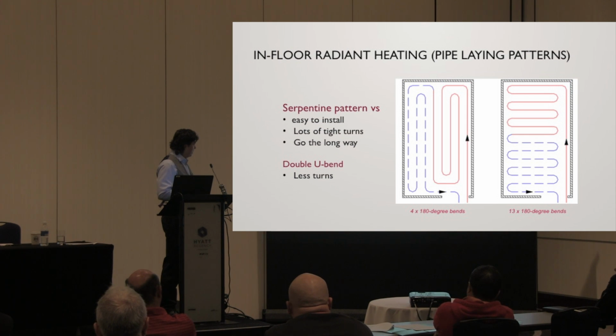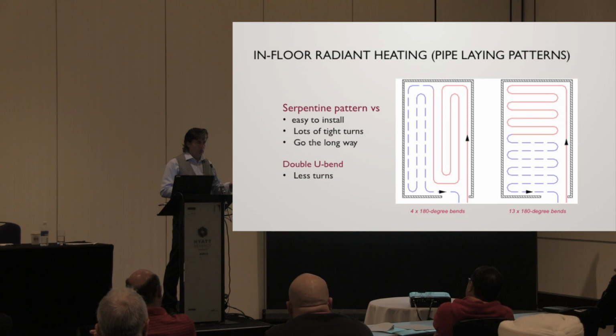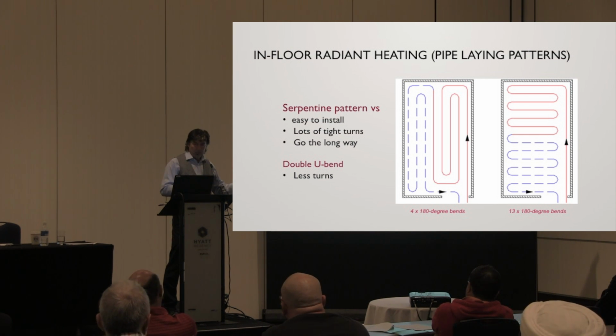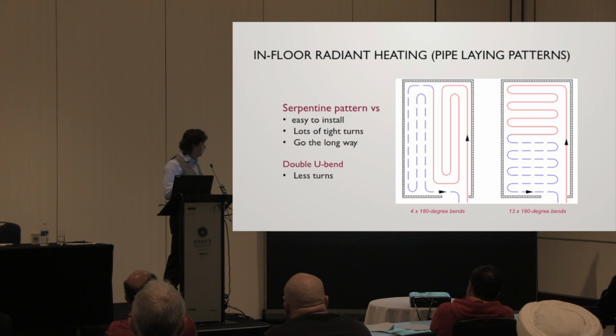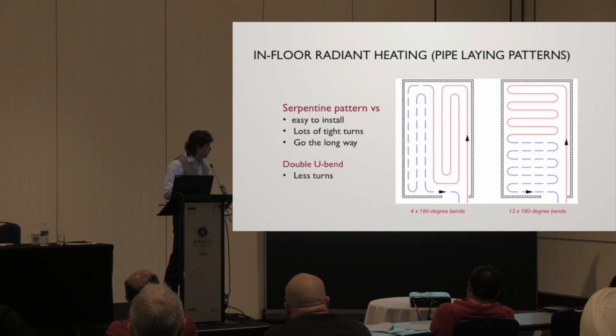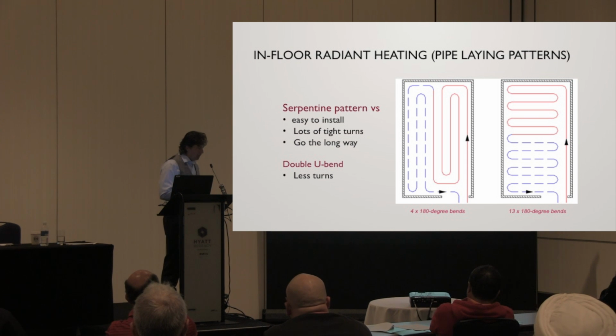And go the long way. So why would you go the short way and use up all these? Go the long way, for God's sakes, if you can. Unless, of course, you have issues with hardwood floor. I don't know how much we do it anymore, but it used to be 2x4 sleepers when you'd use 3/4-inch, the actual hardwood, not engineered floor, but actual hardwood 3/4-inch. Often it would go on sleepers, so you would wind up with sleepers here, right? So that's pretty much the only thing that's going to regulate which direction you run your loops, if you have sleepers for hardwood floor. Okay? And if there is no regulation, why not go the long way? Less bends.